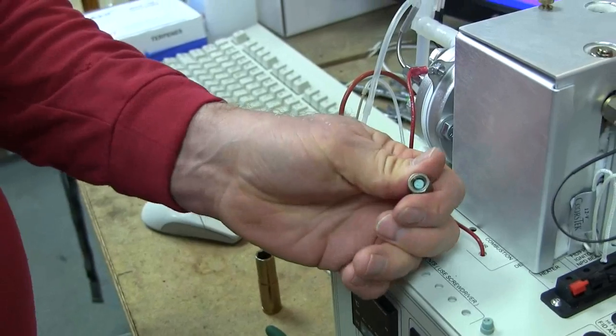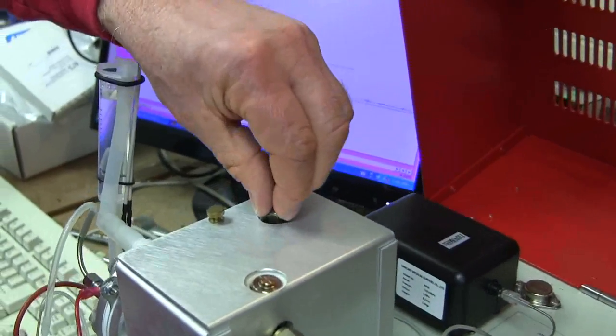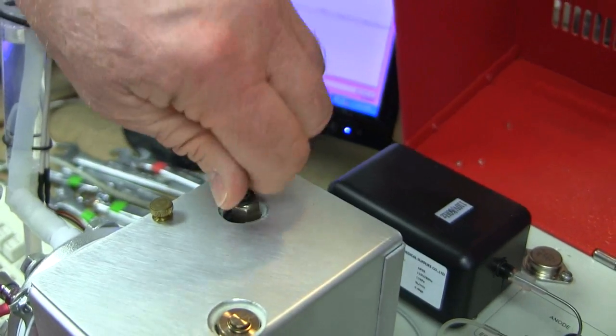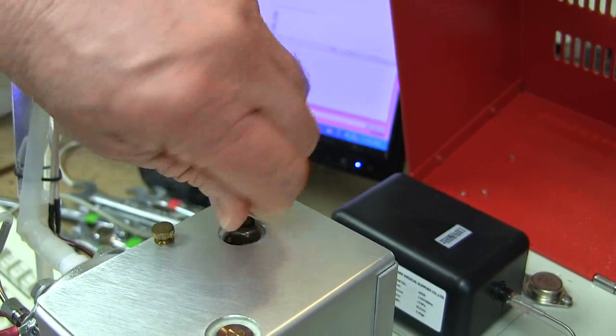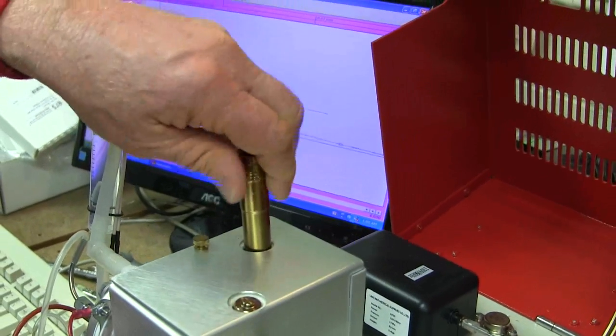Okay, so that's the new septum that's in there. And then we're going to put the nut on top of the septum and then tighten. So this is the step that you have to be a little careful because you don't want to get it too tight. You can over tighten it, but it really only has to be just a little bit past finger tight.